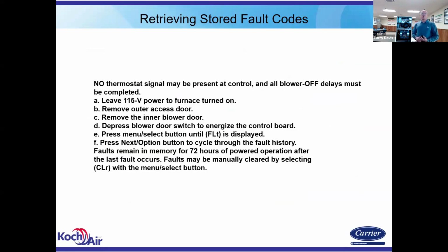Retrieving stored fault codes. You can retrieve it from the board. You want to make sure it doesn't have a call. You power it up, you pull the door off and you scroll through and you find your faults. You go to the fault menu. Again, it holds them for 72 hours and you can clear that out. So I recommend after a service call or after any time you touch that, if there's any faults in that current history, clear it out.